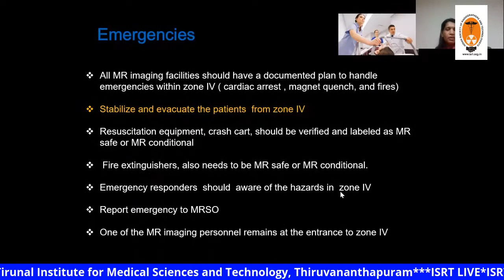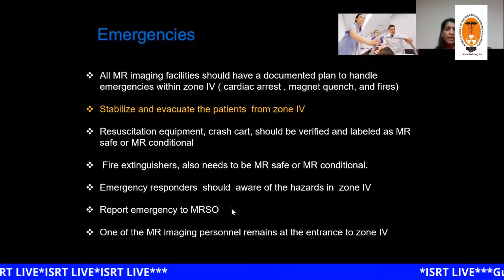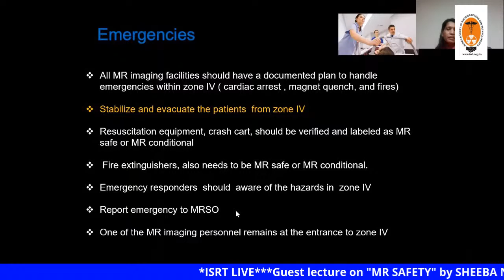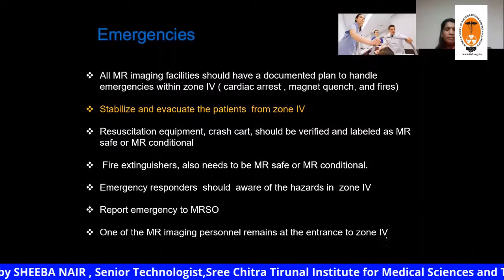We have to keep an MR safe fire extinguisher near the MR room, and all emergency responders of the institution should be aware of the hazards of zone 4. Any emergency that occurs should be informed to the MR safety officer first, and he should rush to the area before other people enter. And one of the imaging personnel should remain at the entrance of zone 4 during an emergency management procedure.